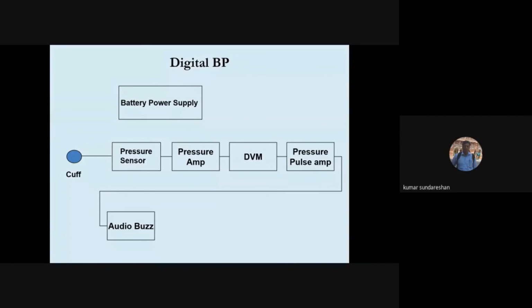So once the pressure is inflated to an adequate level, well above the arterial pressure, it stops and then starts slowly to deflate, and the sensor starts picking up the turbulence, is able to pick up the information, the systolic and the diastolic. And then you also have the audio information if required, you can have it.